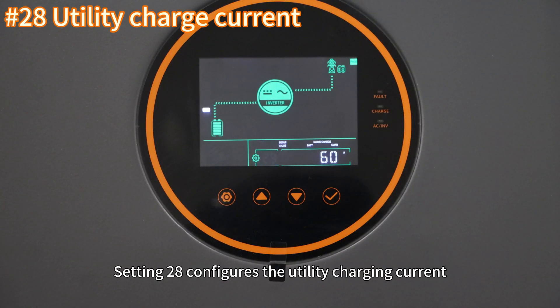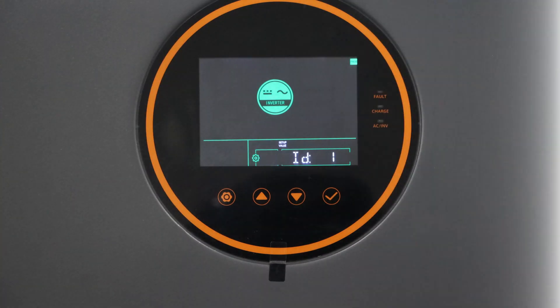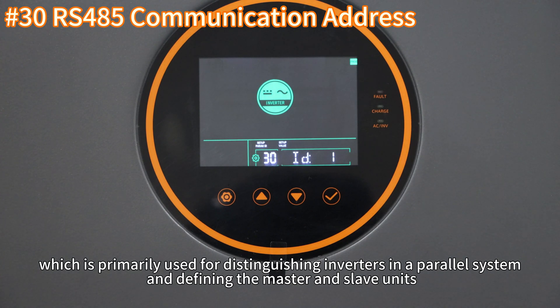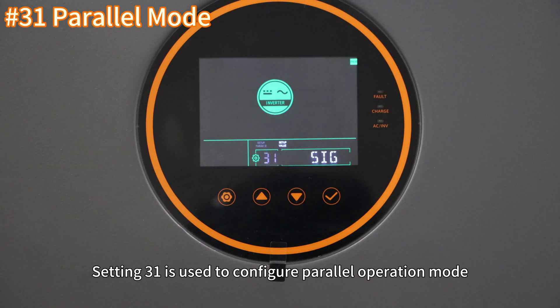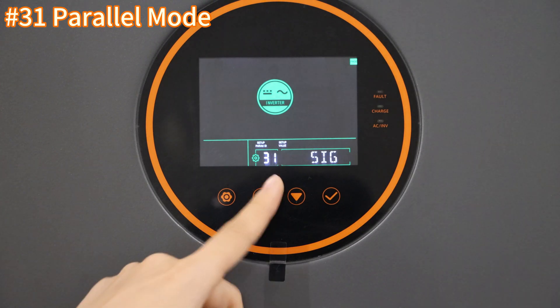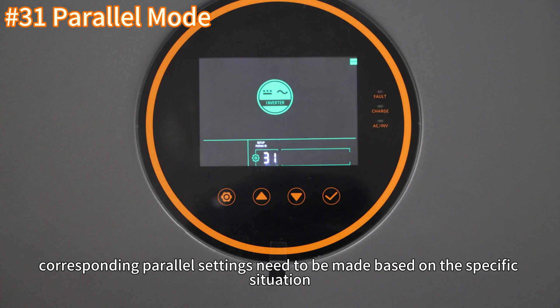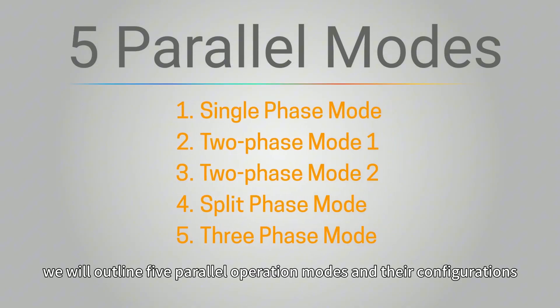Setting 28 configures the utility charging current; the maximum utility charging current can be set to 80 amperes. Setting 30 configures the RS485 communication code, which is primarily used to distinguish inverters in a parallel system and define the master and slave units — no manual configuration is required. Setting 31 is used to configure the parallel operation mode. If a single inverter is operating independently, select SIG. If multiple inverters are operating in parallel, corresponding parallel settings need to be made based on the specific situation.